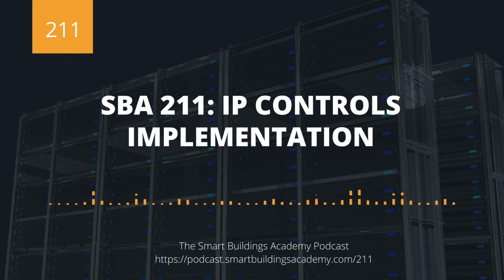Now, if this was a hospital or a critical environment, I may recommend putting graphics in the IP controllers at the air handling units and making them individually capable of running their terminal units and their air handling units, but yet still mirroring the graphics in the supervisory device. So it's a little bit of redundancy, but it also enables us to still have that ability to go to the supervisory device for a single point of graphics.